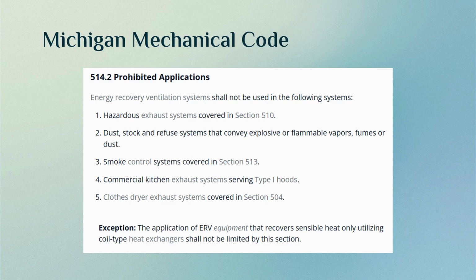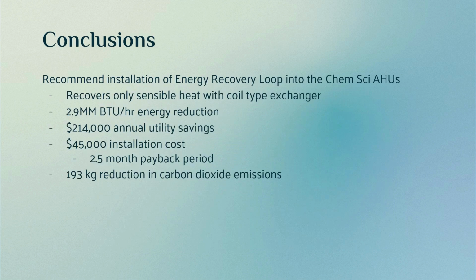However, Michigan Mechanical Code prohibits the application of energy recovery ventilation systems into hazard exhaust systems, which does apply to the entire HVAC system for the chemical science and engineering building, since we do have hazard exhaust from the labs. However, there is one exception, which is the application of energy recovery equipment that recovers only sensible heat utilizing a coil-type heat exchanger. So for this reason, we are recommending the installation of the energy recovery loop into the ChemSci's air handler units.